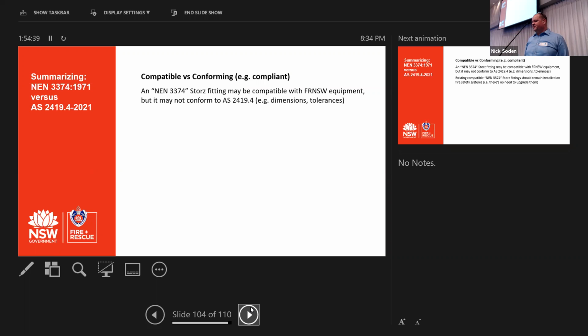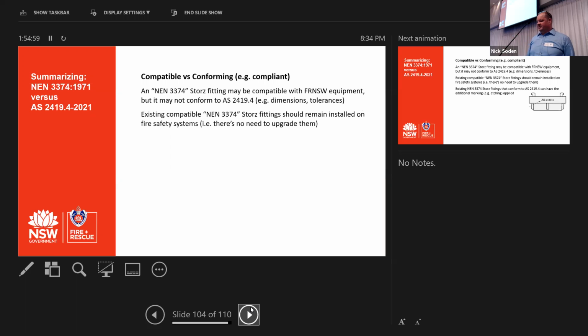An NEN 3374 Storz fitting may be compatible with Fire Rescue New South Wales equipment. However, it may not conform to 2419 Part 4, i.e. the dimensions and tolerances, the interconnection torque might be slightly out of whack. Existing compatible NEN 3374 should remain installed on fire safety systems. We're not asking anyone to remove them and replace them with new compliant Storz. There's no need to upgrade what's on systems already.